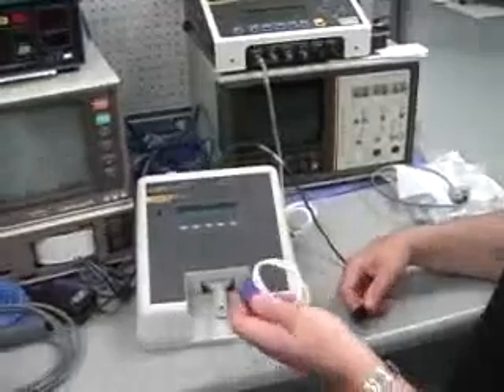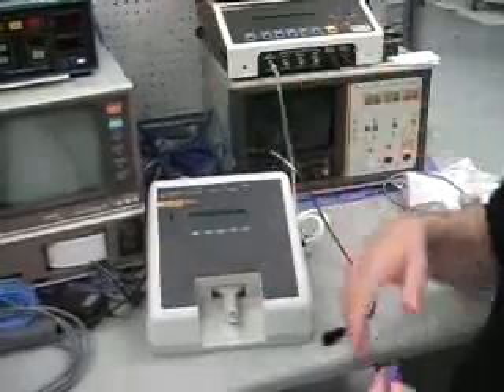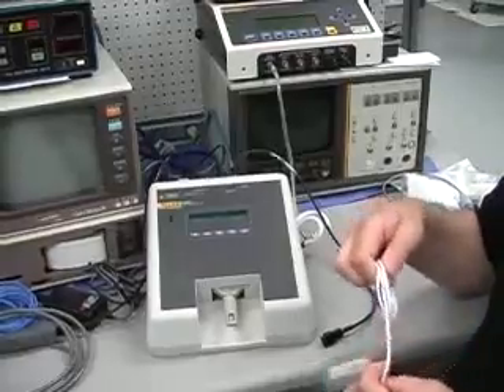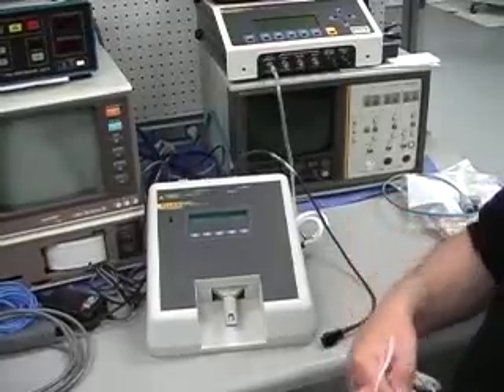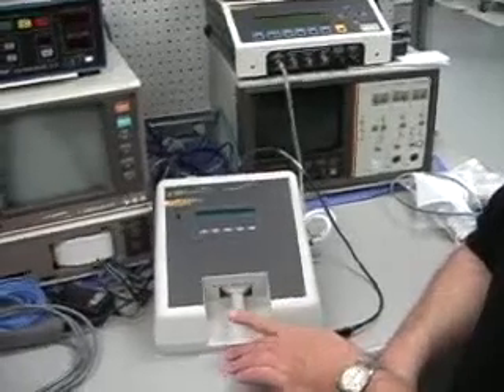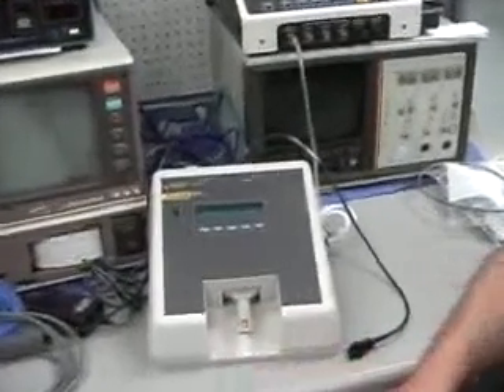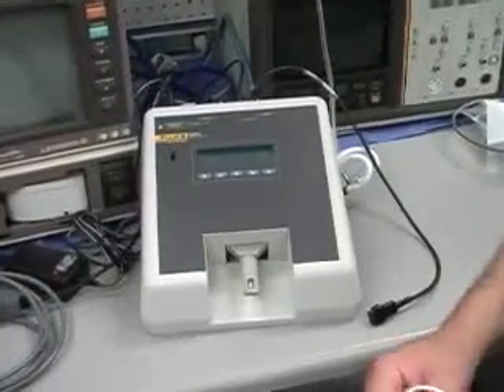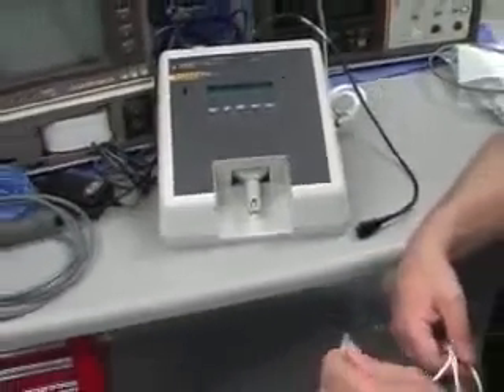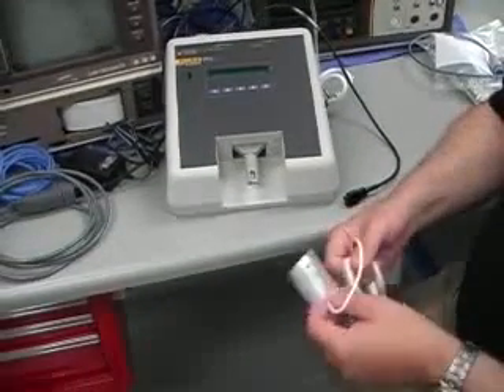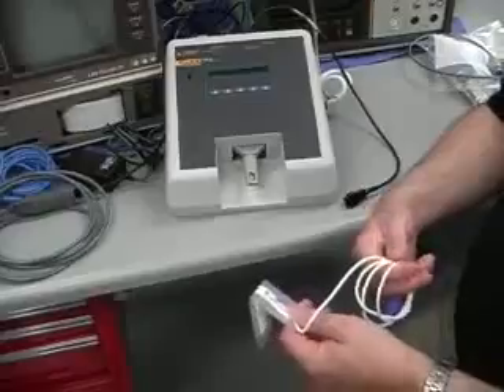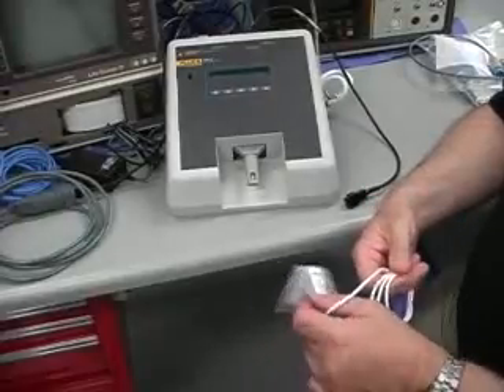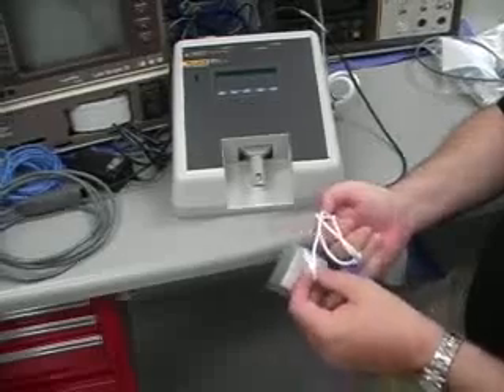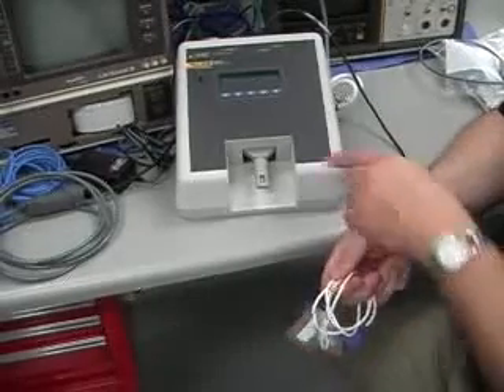and you can do that by eliminating the optical sensor within the system, so that you're just testing the basic electronics of the device. Or if you're looking to do more of a complete system test, you can also do your testing via the optical finger on the front of the instrument. Obviously, you'll only use one at a time, because you have to synchronize the operation of the index with that of the monitor. So it can only use one active input interface at a time.